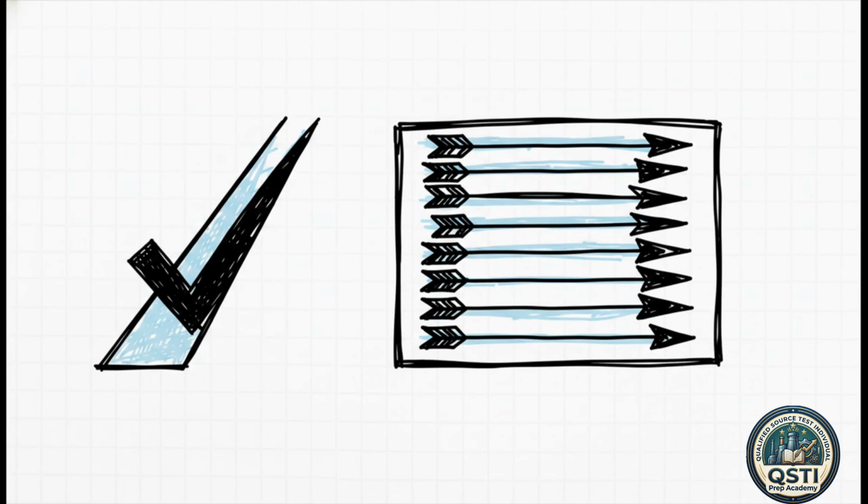So here are your final acceptability criteria for those really tight alternative spots. Your average resultant angle still has to be less than or equal to 20 degrees. But on top of that, your standard deviation must be less than or equal to 10 degrees. Hitting these numbers proves that not only is the flow mostly straight, but it's also highly uniform without any crazy fluctuations going across the duct.